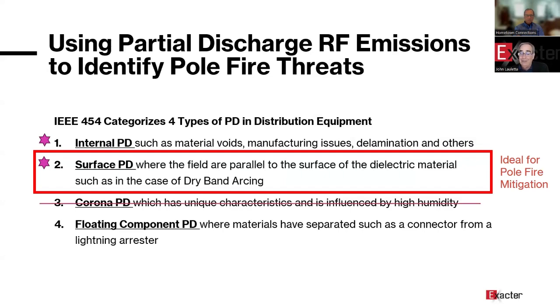Corona PD, like I said, doesn't really apply much to distribution, but where it does, it's not a really good indicator of deteriorated equipment that's an incipient failure. Because in high humidity or light rain, dew, moisture, you're going to get PD from Corona on anything that is in the right voltage level, which I believe is above 37 kV, where Corona exists. That problem is, it just tells us we can't use that as an indicator of incipient fault. It may not be what you want. It may cause TVI and RFI problems, but it's not an incipient fault problem.